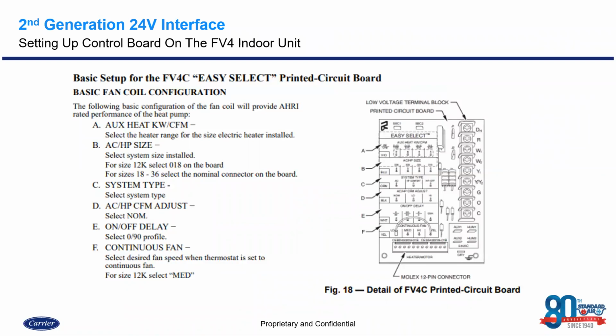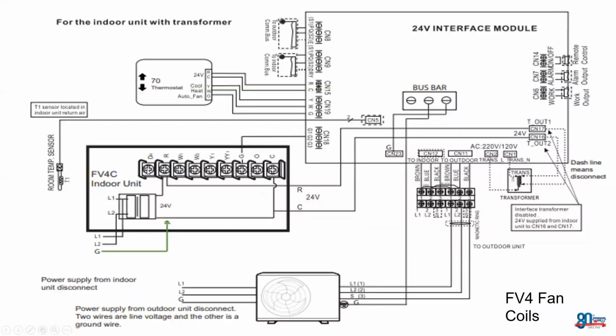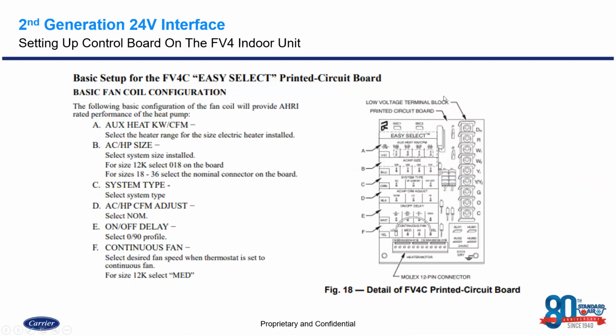Okay, so now that we have the wiring set up on here, we want to look at the printed circuit board of that FV4. I'll flip back to the previous slide. What we're looking at right here now is what you're actually going to see at the furnace. So this is where you're going to have an R, a C, and a G connector. Now we need to look at the easy select tabs on here to make sure that we have this set for the appropriate combination, depending on the tonnage of the unit, the CFM adjust, and the on-off delay that we want, which is fully customizable. So if we have some form of auxiliary heat, we need to look at tab A and make sure that we set it to the appropriate kW that we have attached to the system.